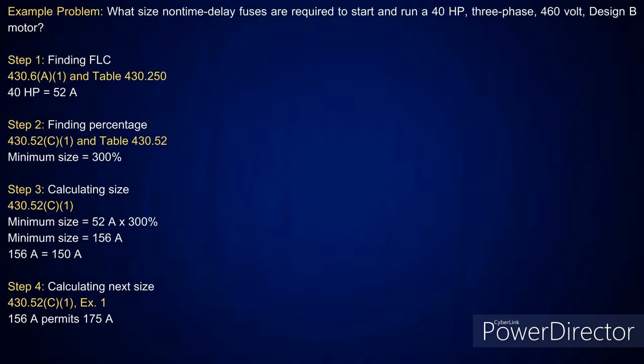All right? So if you look at 430.52(C)(1), and this is important, and I want y'all to pay attention to what I'm telling you here. You're going to look at that section, and I want you to look at what it says. It says, in accordance with Table 430.52. Now, if I'm in the 2023, it's going to say (C)(1). But the main thing is when it says in accordance with Table 430.52, it says a protective device that has a rating or setting, now listen to this, not exceeding the value calculated. So if you can't exceed it, that means you have to do what? Drop down.